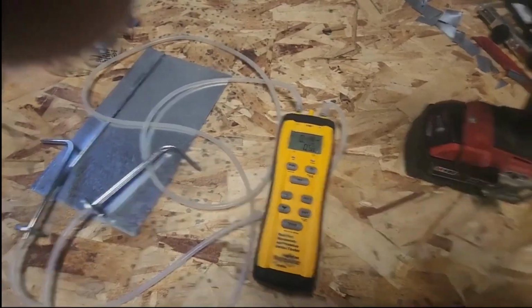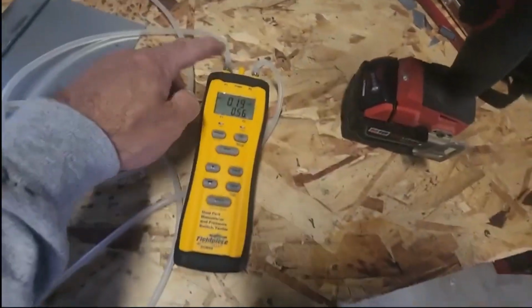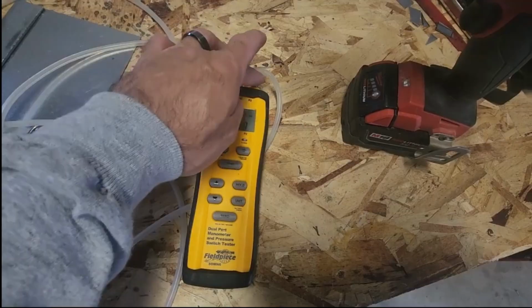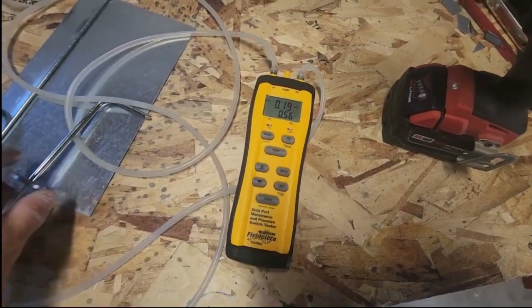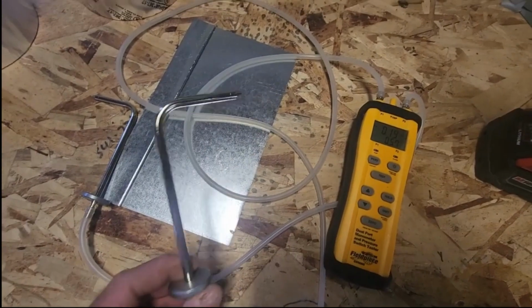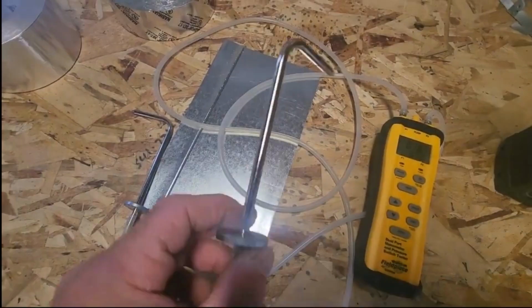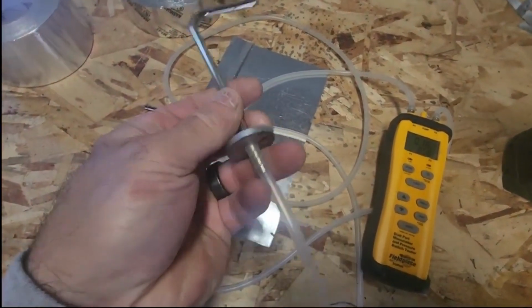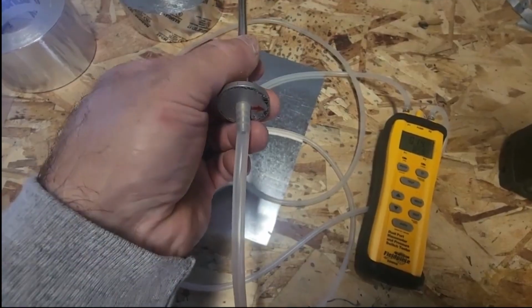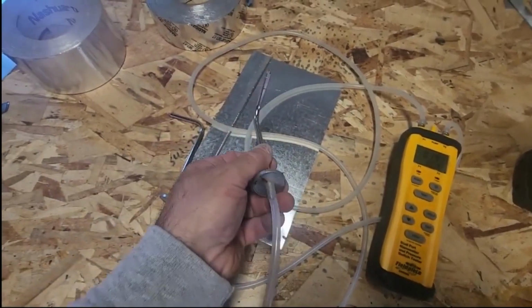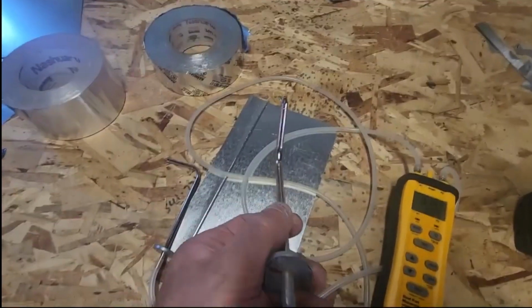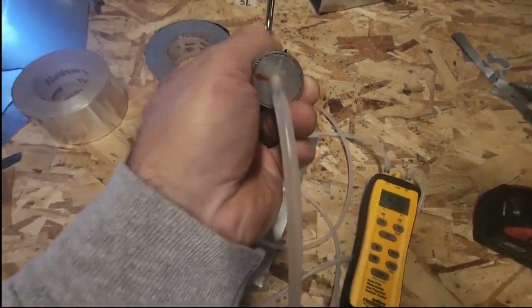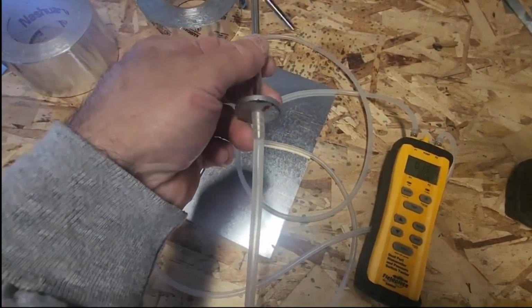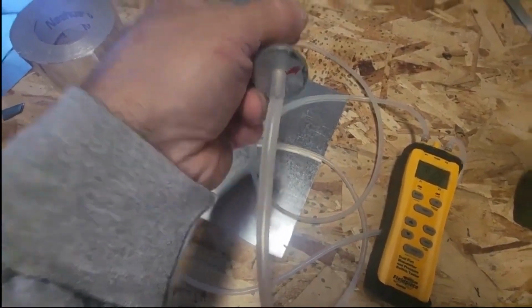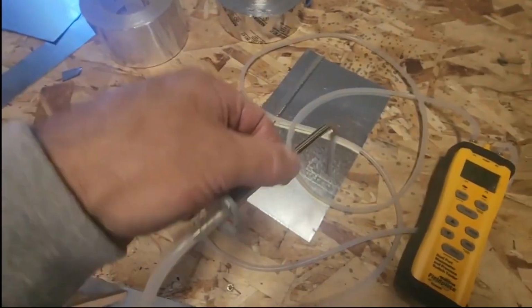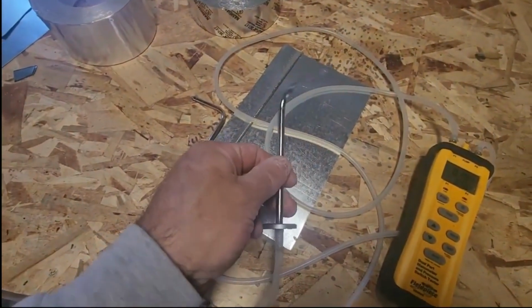So what you need is your manometer and a length of tubing to go into port 1 and port 2. This is going to be one for the supply and one for the return duct. Each one has a static pressure tip, and these tips must point into the airstream. Mine kind of screwed up, so the swivel on it is broken. I'll just have to make sure that it's going into the airflow. On my downflow air handler, it's going to need to point up like that, and the same with the return. If you had an upflow, it'd be opposite. You'd have your tip pointing down and your return pointing down to orient it.